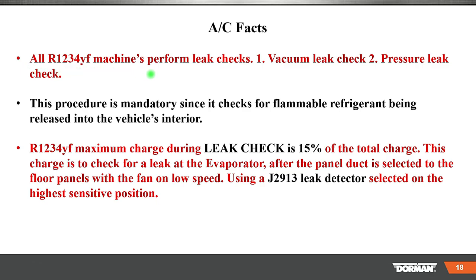All 1234YF machines do this: a leak check, vacuum leak check, a pressure leak check. This procedure is mandatory since it's checking for flammable refrigerants. The maximum charge for a leak check is 15%. That was the question that a couple of guys won a couple of Dorman t-shirts for.